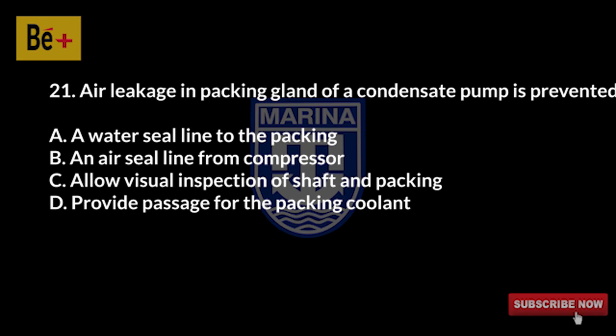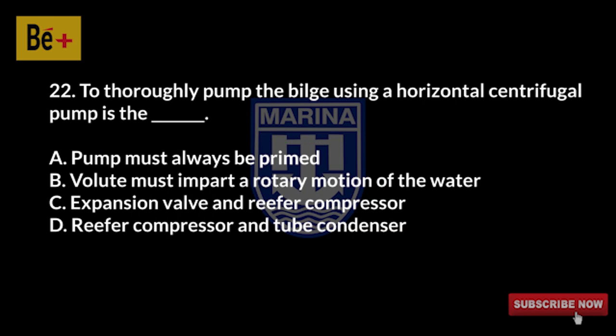Air leakage in the packing gland of a condensate pump is prevented by: A) a water seal line to the packing, B) an air seal line from compressor, C) allow visual inspection of shaft and packing, D) provide passage for the packing coolant. The answer is A, water seal line to the packing.